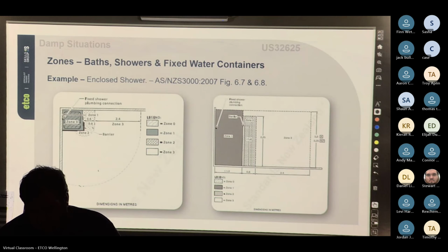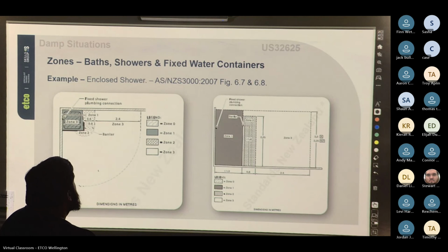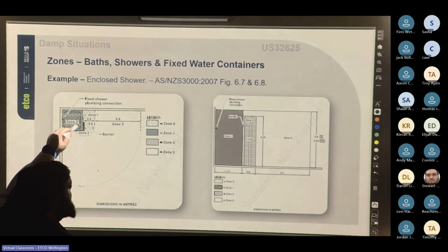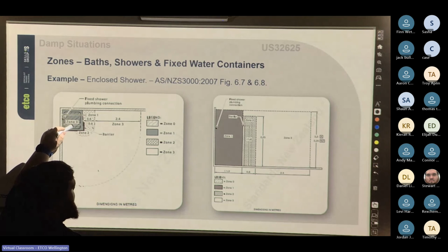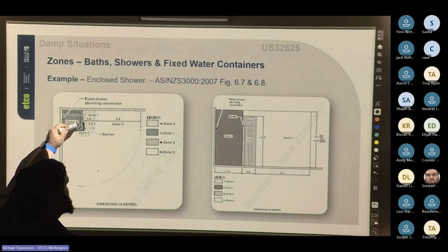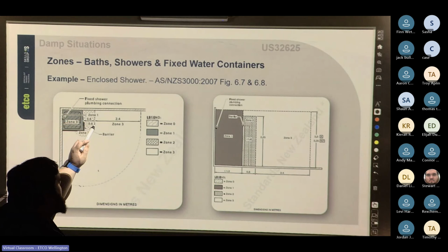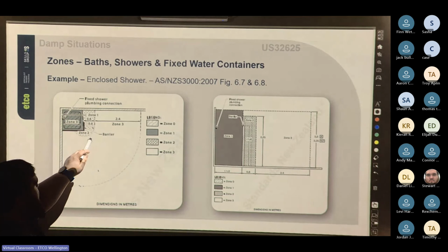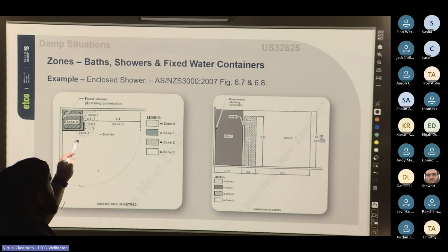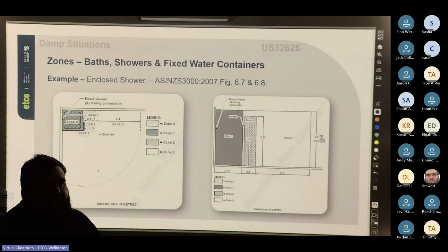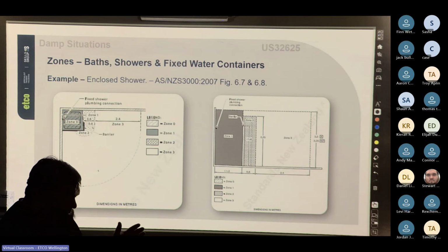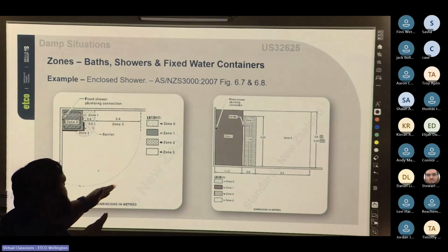Cool. And then we go to an enclosed shower. It's enclosed, but it has a door. So zone 0 is our bathtub pan, zone 1 is the area above it, and zone 2 is 0.6 meters directly out from where the door is. Then, using the pivot pinch point of the door as our pivot point, we create another 0.6 meters for the barrier. Similar to the bathtub, where the fixed part of the enclosure ends is where we draw our 0.6 meters, using it as the center point of our compass. So where the door opens, 0.6 meters out from the pivot point on the door, is a 0.6 meter radius around that. And then we draw our zone 3 to match that as well.